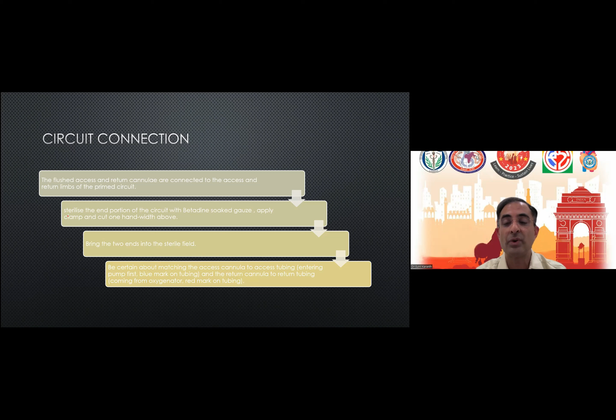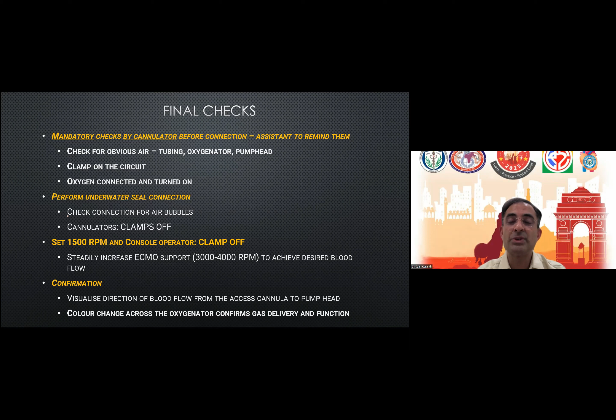Perform all the necessary underwater seal. Once the patient is on ECMO, start with an RPM of 1500 and gradually increase as per the patient's needs. Confirmation is often got by the visual direction of the blood flow from the access cannula to the pump head and the color change that runs across the oxygenator, ensuring that there is optimal gas delivery and function. Of course, after this, you would also look at the patient's hemodynamics, saturation, and the subsequent ABG, which will ensure optimal maintenance of the ECMO. Thank you.